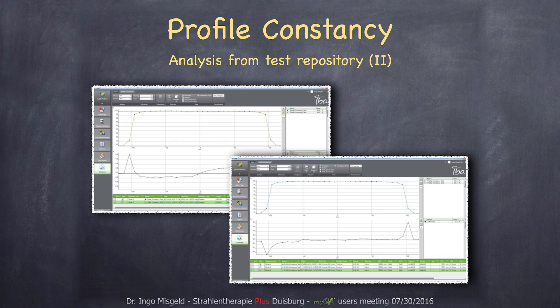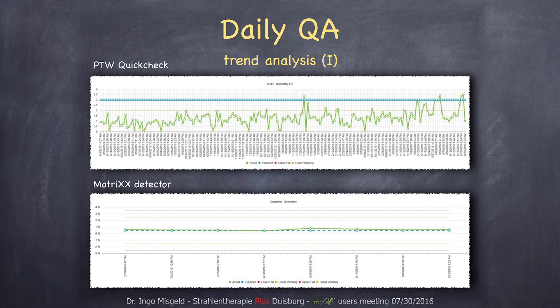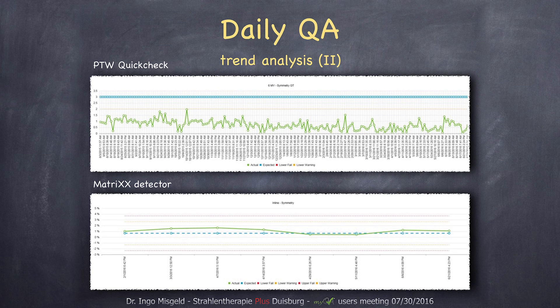The last point I want to talk about is daily QA. We use the PTW Quickcheck device every morning for different parameters. For example, the symmetry parameter. As you can see, there's a large scatter in this data and we don't know why. We tried to measure it with different people and tried displacing the detector, but nothing helped. So we started to measure this with the matrix detector, and as you can see, there's no such large scatter. The same is true for the other machine we have. It looks like the matrix detector is much more stable in providing these parameters.